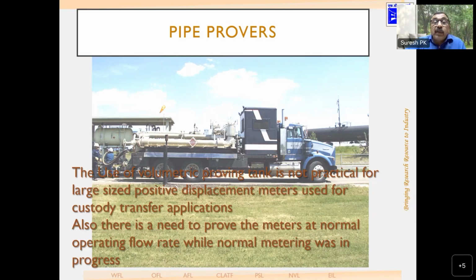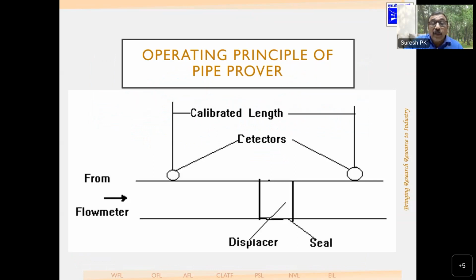So in order to overcome that problem, there are pipe provers which are used for the calibration of large size flow meters. Whatever comes through the flow meter passes through a calibrated length of pipe, and you have a displacer here. The displacer is moved from one point to another point, and the volume between the detectors is fixed and calibrated. Therefore, the volume indicated by the flow meter can be compared with the calibrated volume between these two detectors. When the displacer moves across a detector, it gives a signal, and it moves slowly through the pipeline until it reaches the next detector.